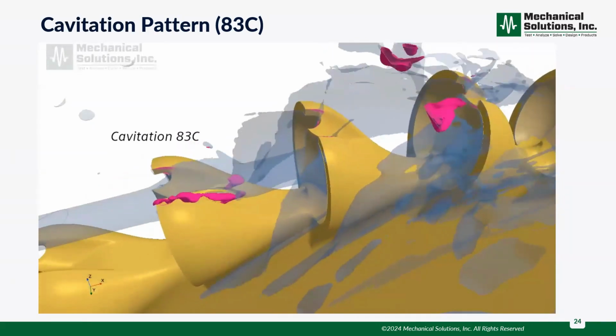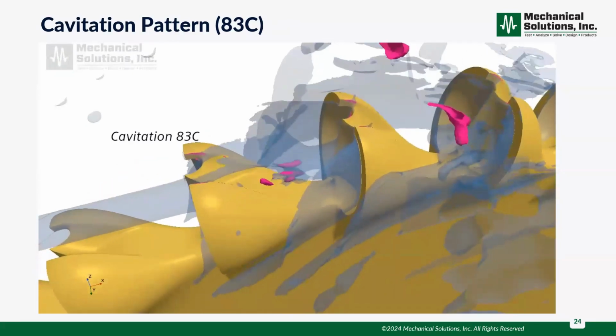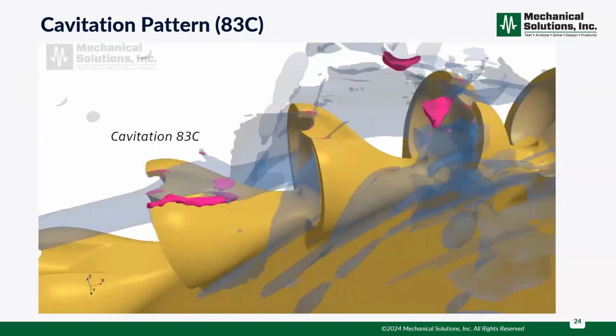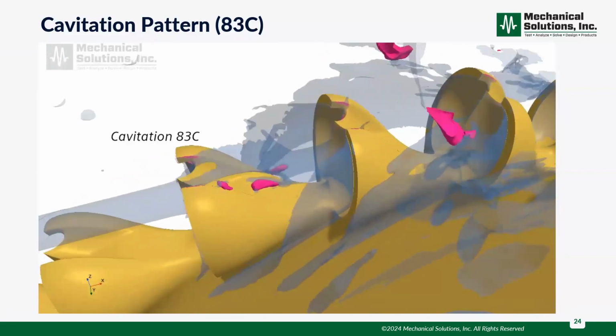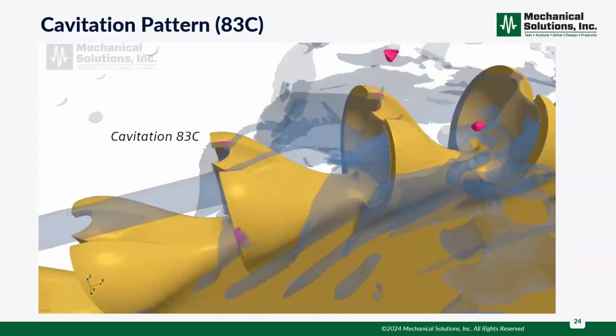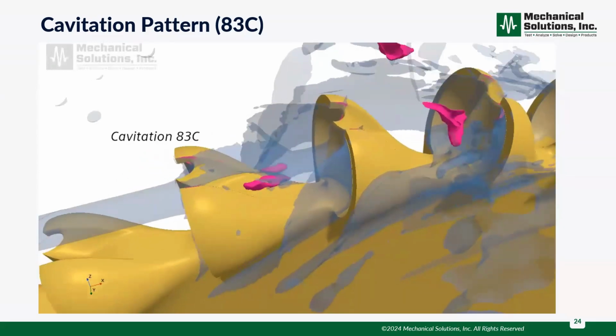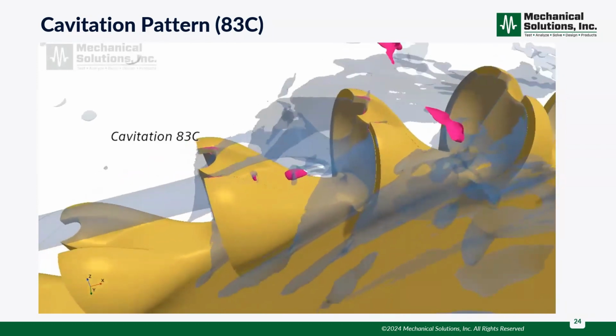So a way to improve that, a very simple one, could just be the operation. If you spin the wheel a little faster, you probably get less of those losses because you turn more of the forward impulse into torque. So matching the wheel speed to the jet. The wheel speed, yeah. But often the wheel speed is limited by the generator, right? So it's fixed. So inversely, you could also slow the jet down. You could say, hey, we dial the jet down a little, and maybe we're getting less loss, and we're just tuning it to get to a bit higher efficiency.